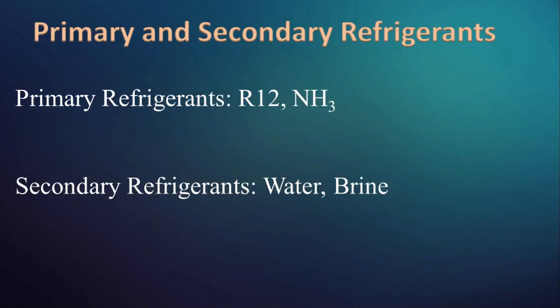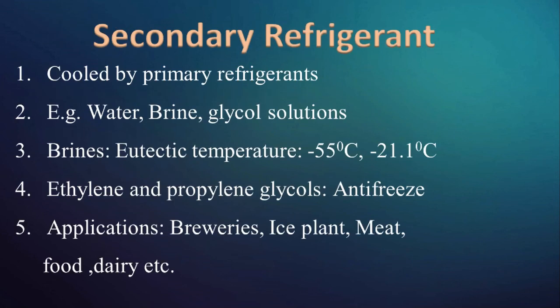Refrigerants are also classified as primary and secondary refrigerants. Primary refrigerants are the ones which are directly used as working fluid in the system, whereas secondary refrigerants are cooled by the primary refrigerant first and then used to cool the substance or space. The refrigerants discussed earlier are primary refrigerants. Secondary refrigerants include, for example, water or brine. Brine is a mixture of water and salts like sodium chloride and calcium chloride, used for cooling of meat, fish, or in ice plants.